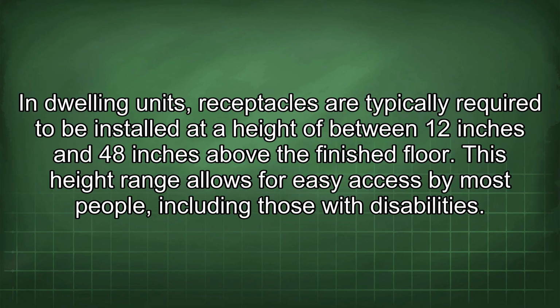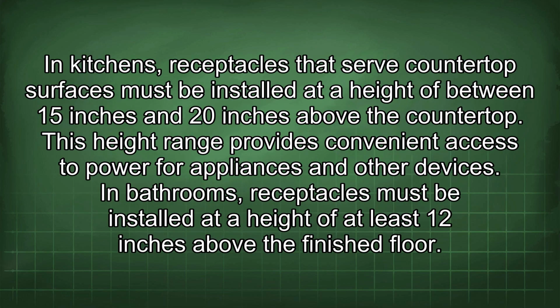In dwelling units, receptacles are typically required to be installed at a height of between 12 inches and 48 inches above the finished floor. This height range allows for easy access by most people, including those with disabilities. In kitchens, receptacles that serve countertop surfaces must be installed at a height of between 15 inches and 20 inches above the countertop. This height range provides convenient access to power for appliances and other devices.